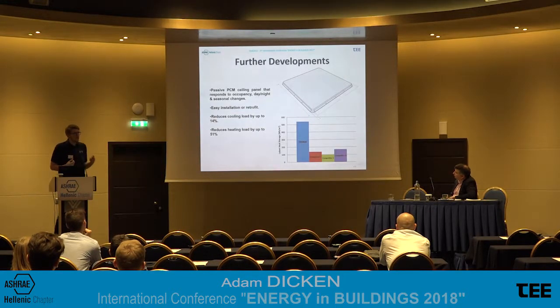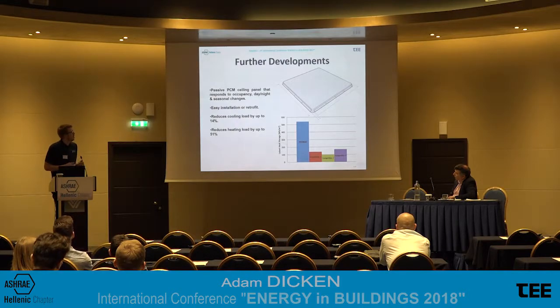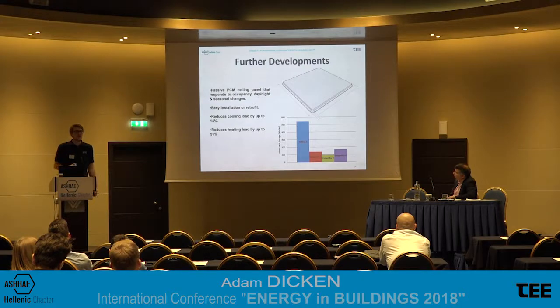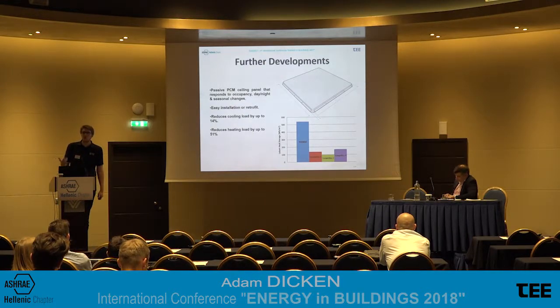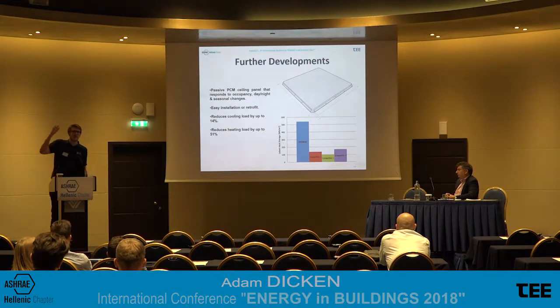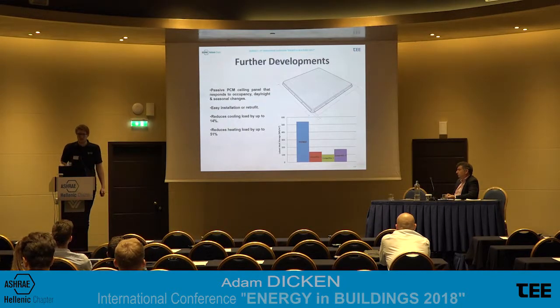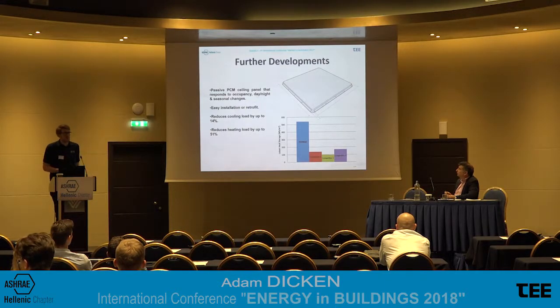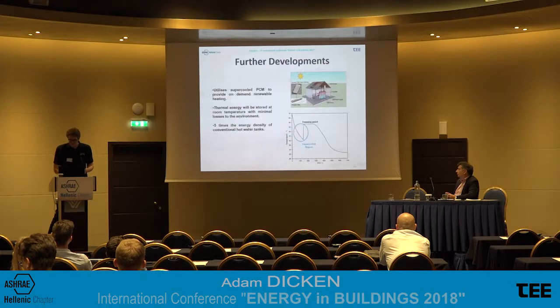Some current developments with PCM: I'm currently working on a passive tile instead of passive tubes in the ceiling. The whole idea of passive is fit and forget, trying to ensure a retrofit is as simple as possible, and also allowing for some spot cooling by placing them directly above things with a large build-up of heat. We're aiming to reduce heat load by 51%, but this is variable based on the percentage of roof covering and things like this.